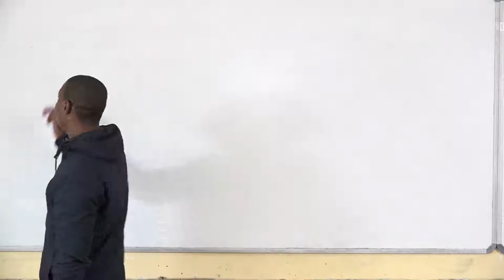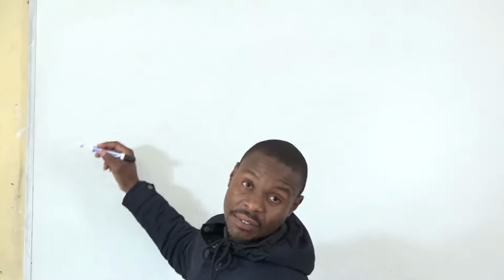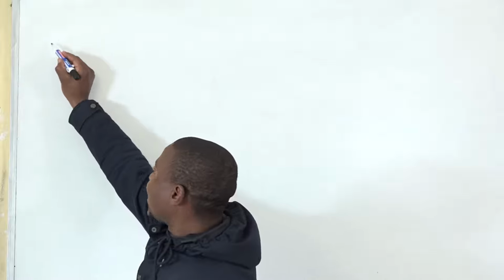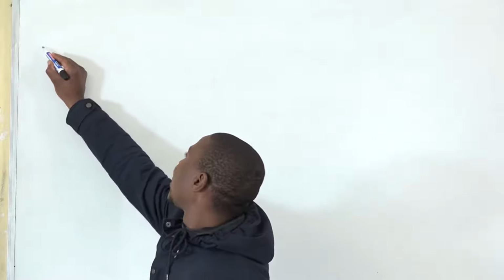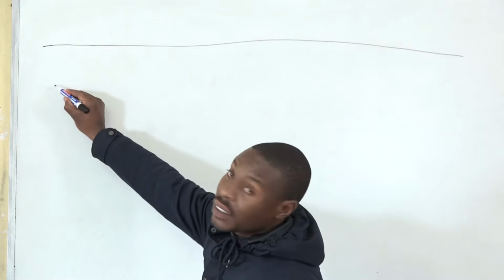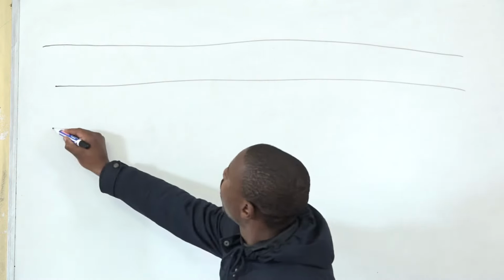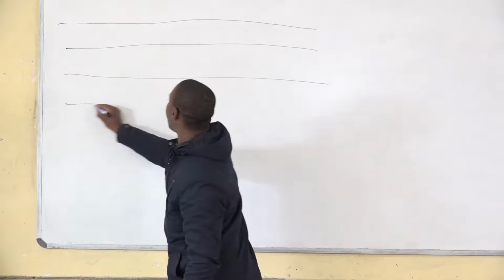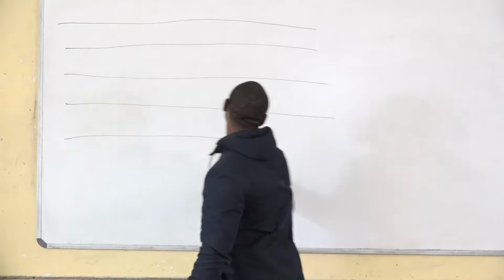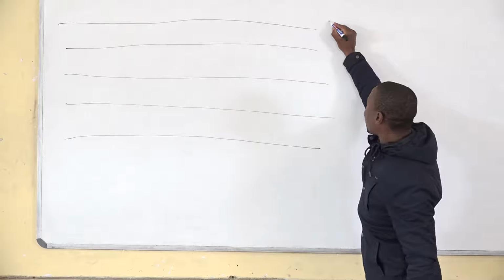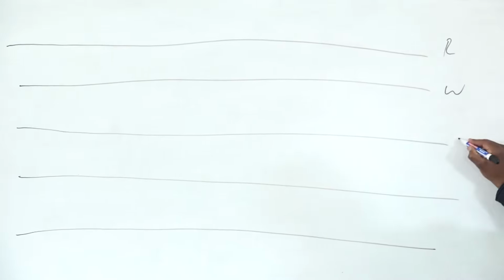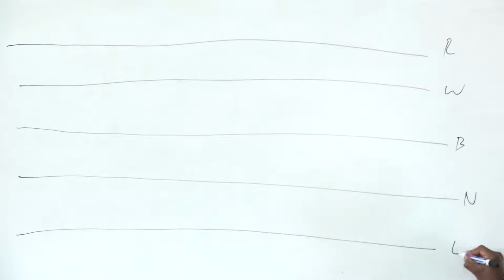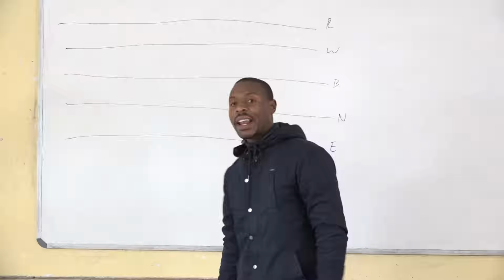Okay, then we said from the secondary side of our transformer, we have what? 5 lines now. That's why we have our 3-phase 4-wire system. These lines are coming from the star point of the transformer. So we still have line 1, line 2, line 3, then neutral and earth. So line 1 can be a red phase, then white phase, blue phase, neutral, and earth. So now we need to balance a load.